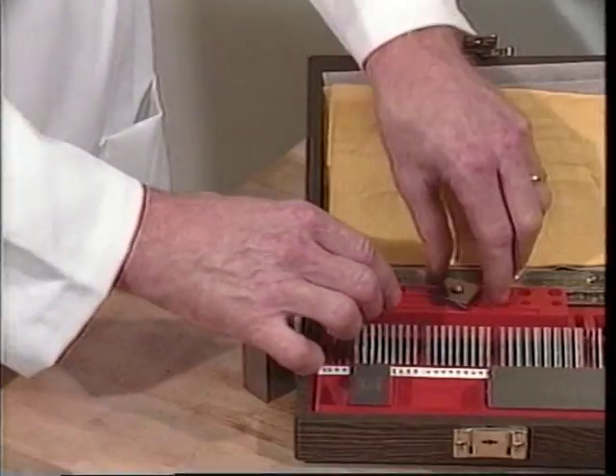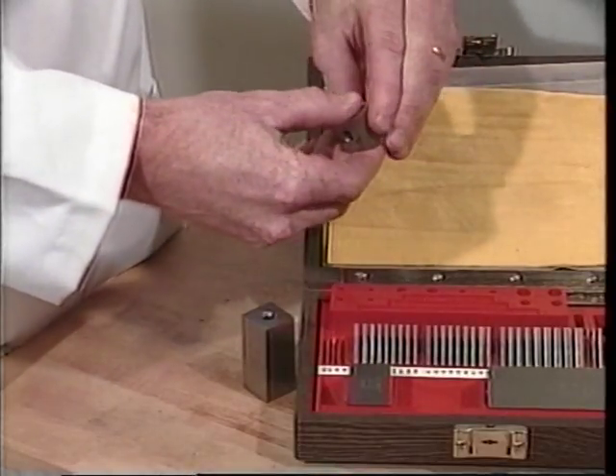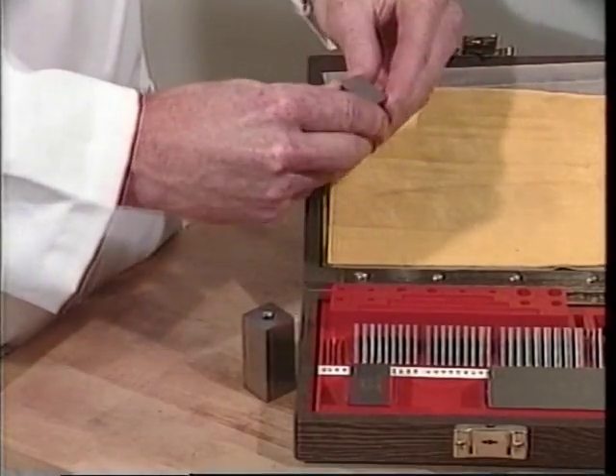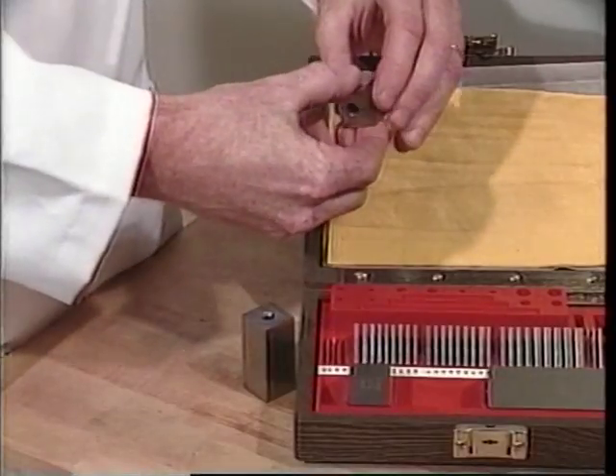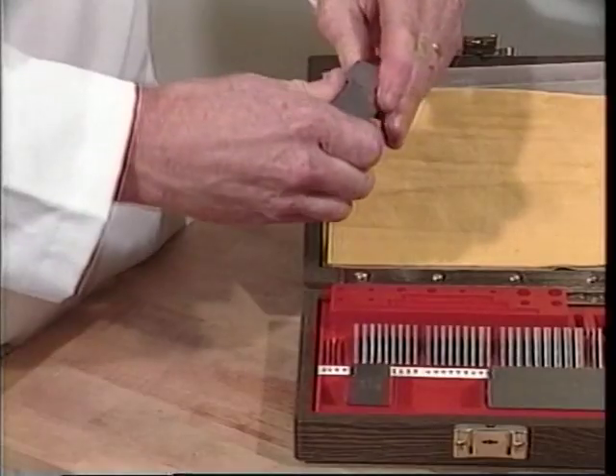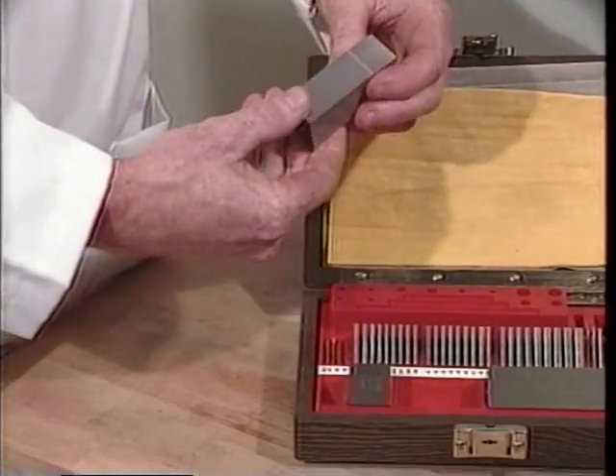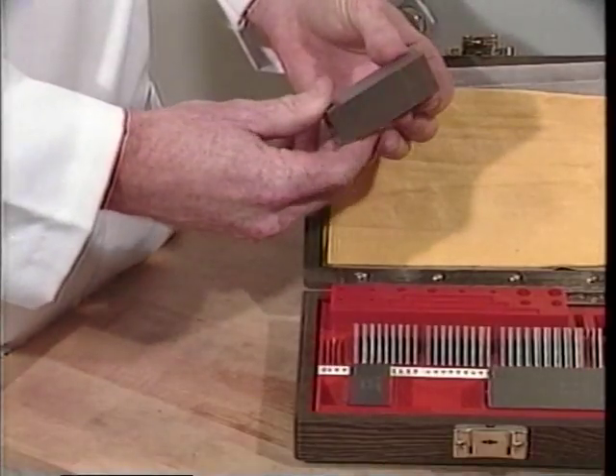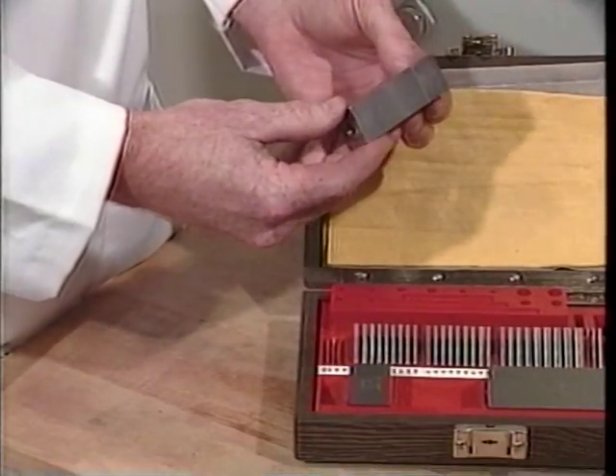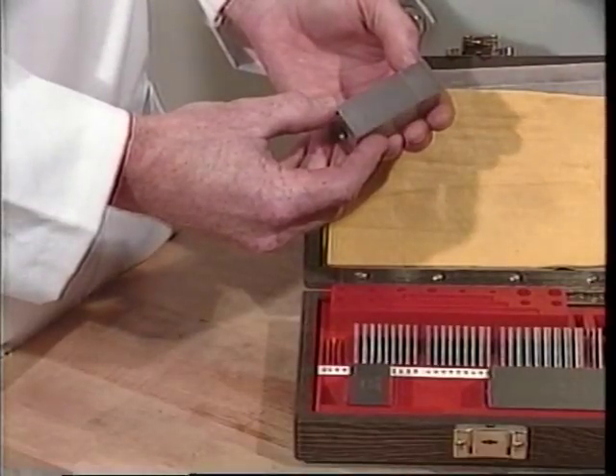Using a basic set of various length gauge blocks, random lengths can be measured by joining the blocks necessary to form a stack of blocks of the desired dimension. The terminal surfaces of the two gauge blocks are wrung or twisted together and held secure by a wringing film approximately 1/4 of a microinch thick. Since these film thicknesses are measurable, the total number of ringing films present should be minimized to avoid undermining the accuracy of the measurement.